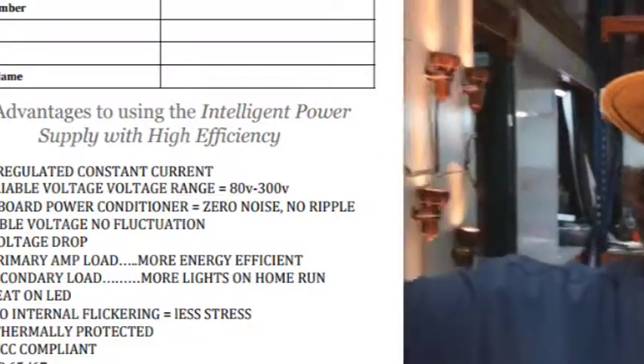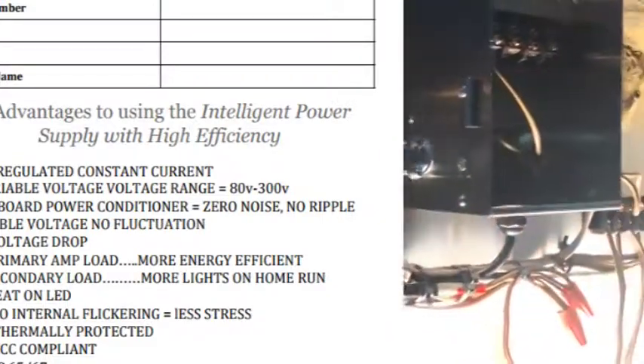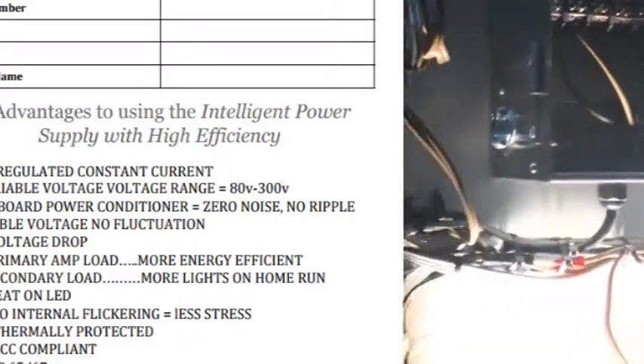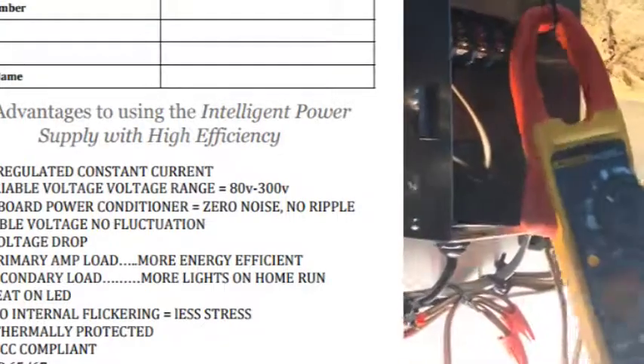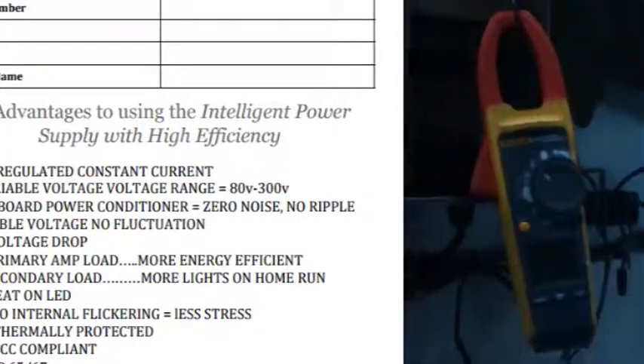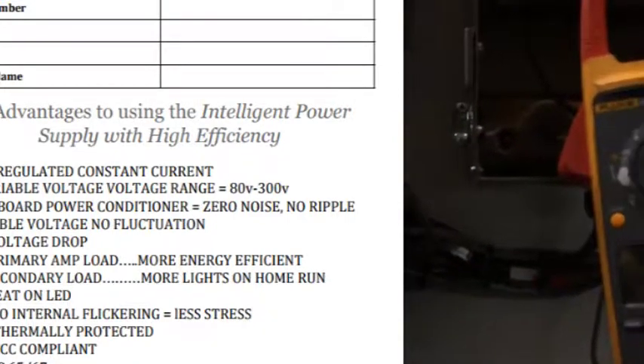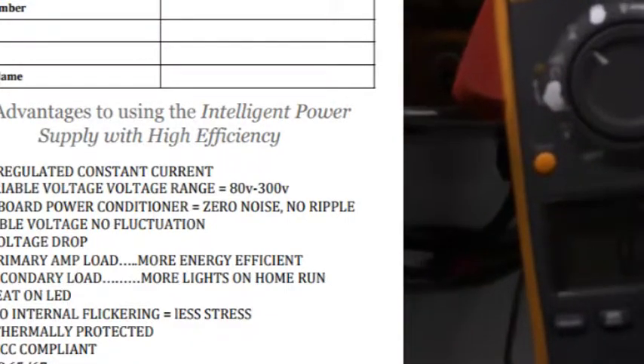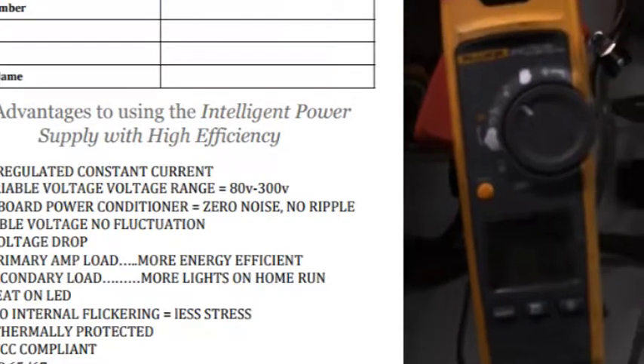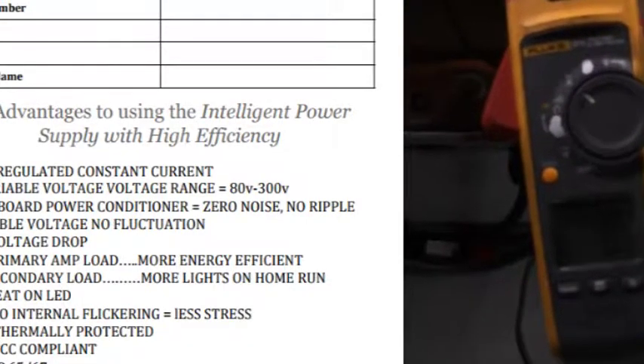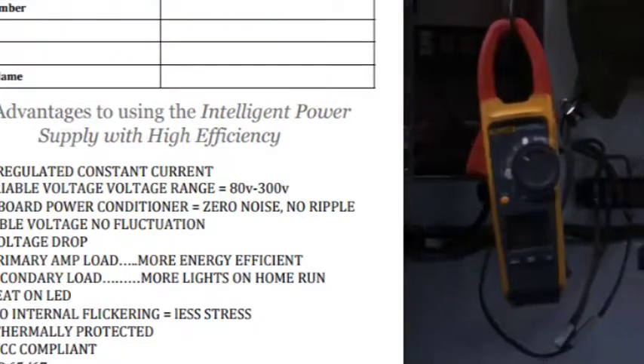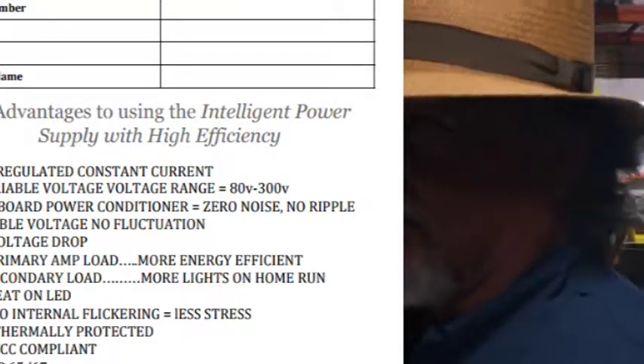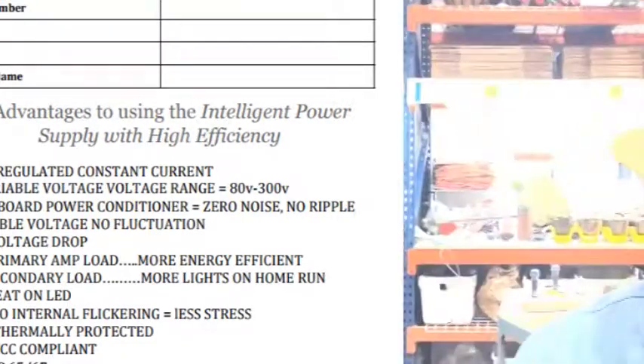If I put an amp probe on this transformer right now, and I will, right? You will see that with zero light bulbs on it, it draws 0.4 of an amp. Zero load. Went down to 0.3. Zero load. These transformers are not energy efficient, right? They're as old as can be.